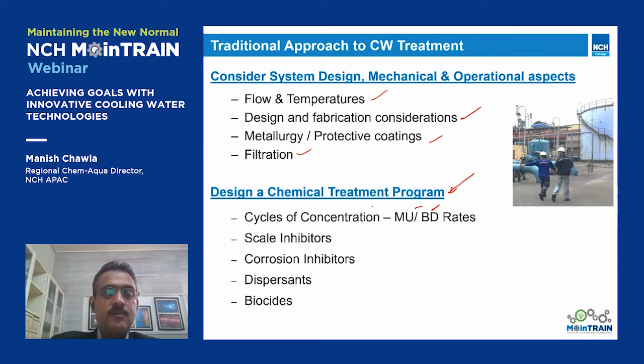We'll collect all these details of the system, and then a water treatment chemical company would design a treatment program. It will decide how much makeup, blowdown, what should be the cycle of concentration, and then decide what chemicals to use.